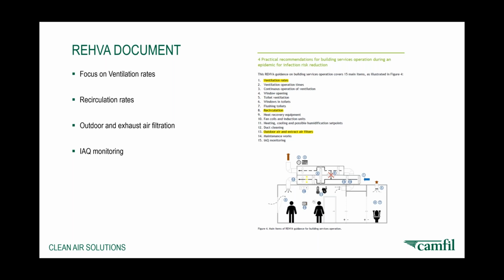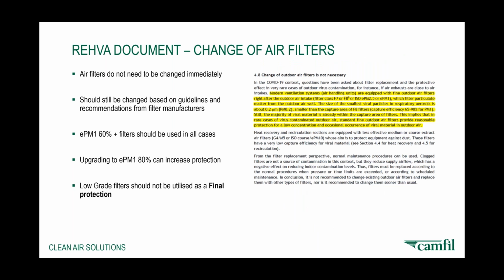Bottom line, they've looked at the type of filters that you can use in your systems. And they also give advice, importantly, bearing in mind that these filters will trap particles on which virus may be present. So what they've said is that air filters in general systems do not need to be changed immediately. So if an air filter is in a system and somebody's infected and we know the filter has captured or potentially captured some virus, it should still be changed based on the guidelines and recommendations from filter manufacturers, from your AHU, air handling unit supplier, or from your service company. They do recommend that ePM1 60% plus should be used in all cases. And in fact, upgrading to ePM1 80% will increase protection.